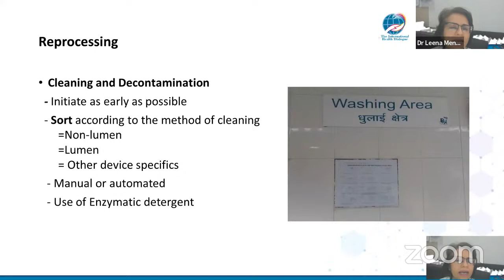Of course, the use of enzymatic detergent is used almost in all, and the manufacturer's instructions need to be followed for how much time you need to be actually immersing in that. Mostly it's an alkaline detergent that is to be used, and you can make use of either manual cleaning or the automated, which may involve the thermal washer disinfector or the ultrasonic, again depending on your type of item that is used. Going on to the drying and inspection part, ensure that it is drying, because any moisture that is left, that item should not be used at all.